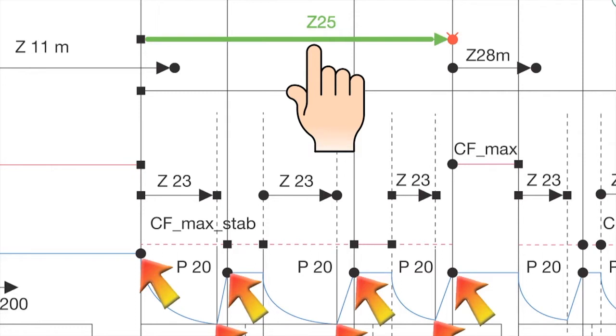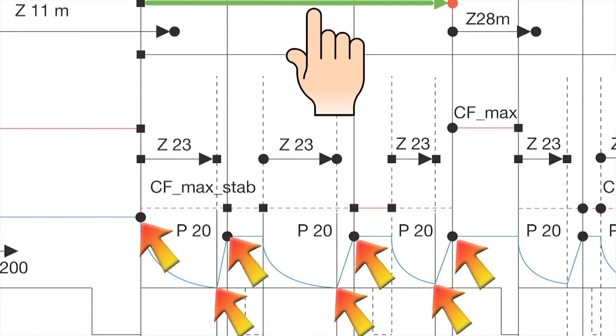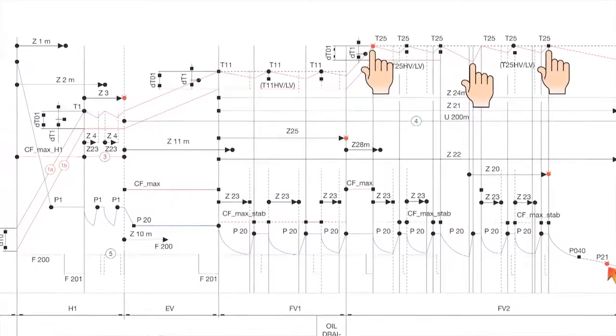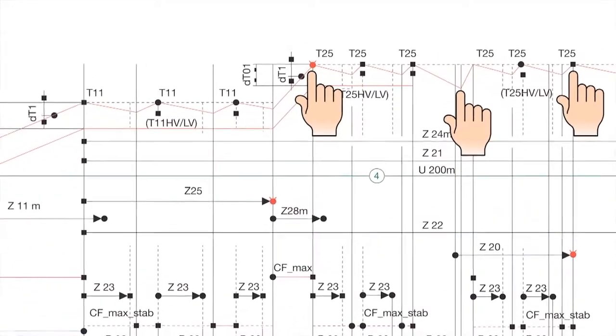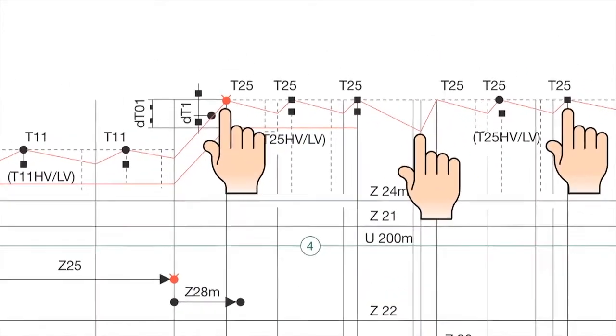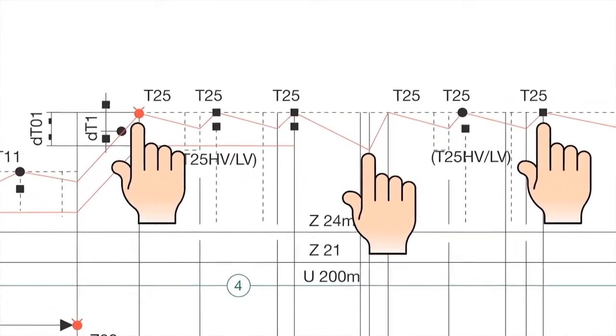Flashovers are prevented through partially breaking the vacuum in the transformer tank with air. After reaching Z25, the process will be switched on to the fine vacuum 2. When oil spray is selected, the oil spray should be stopped at the end of this process step and the oil drained to the storage tanks. Overview. Fine vacuum 2. The transformer will now be heated to the final temperature set point.